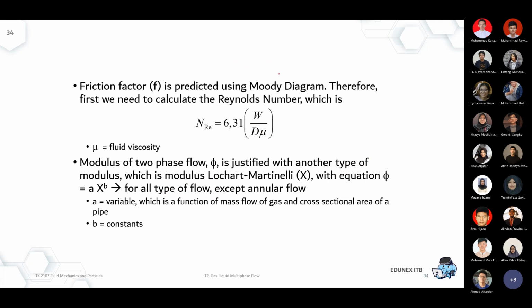In terms of the F, again, you can calculate it from the Moody diagram or the Fanning diagram. Of course, you have to start from the Reynolds number, and remember that you have a function of Reynolds number versus friction factor. That's the laminar part usually, and then you have plenty of other curves for turbulent flow depending on the roughness of the pipeline. It's still the same concept.